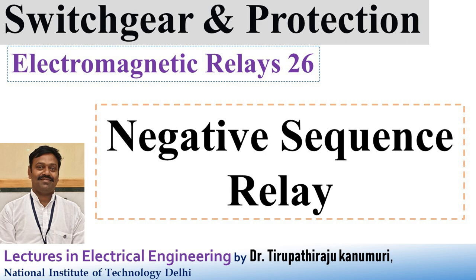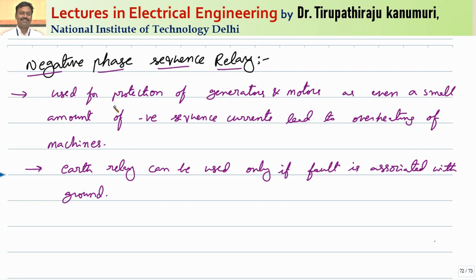Today we are going to discuss the negative phase sequence relay. These are mainly used for the protection of generators and motors because the negative sequence currents rotate in the opposite direction to the positive sequence. The negative sequence components rotate at two times the synchronous speed with respect to the fundamental frequency, causing huge induced EMF values, leading to significant overheating of machines. Even a small component of negative sequence can lead to a huge heating problem, and negative sequence harmonics will also be very large. This should be immediately detected and disconnected.